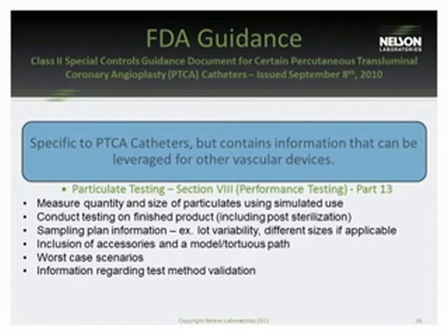Inclusion of accessories and a model or a tortuous path. We'll talk a little bit more about the tortuous path, but basically it's inclusion of devices or models that help model the clinical use of the product. Also worst case scenarios and testing to a worst case scenario. And then information regarding the test method validation, with some specific numbers that are given, which I have later in this presentation. But like I say, they like to see about 90% recovery on those particulate sizes.